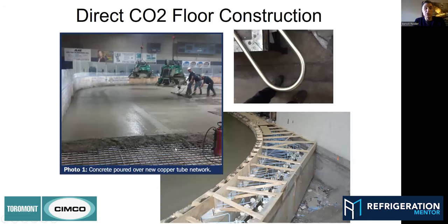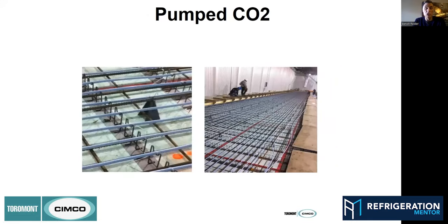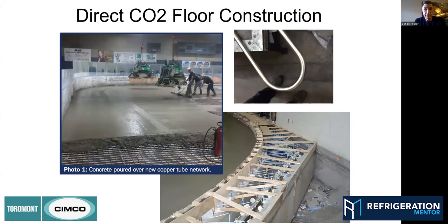And a typical CO2 floor would look like that. This is the one with copper piping, and you can see the copper piping going to the other. And this one was done with stainless steel. Actually, we went with half inch stainless steel tubing in 400 foot rolls, that we unrolled along the whole length of the ice rink, and then we bent it at the end and came back. So we minimized the amount of welding just by bending the pipe like that.